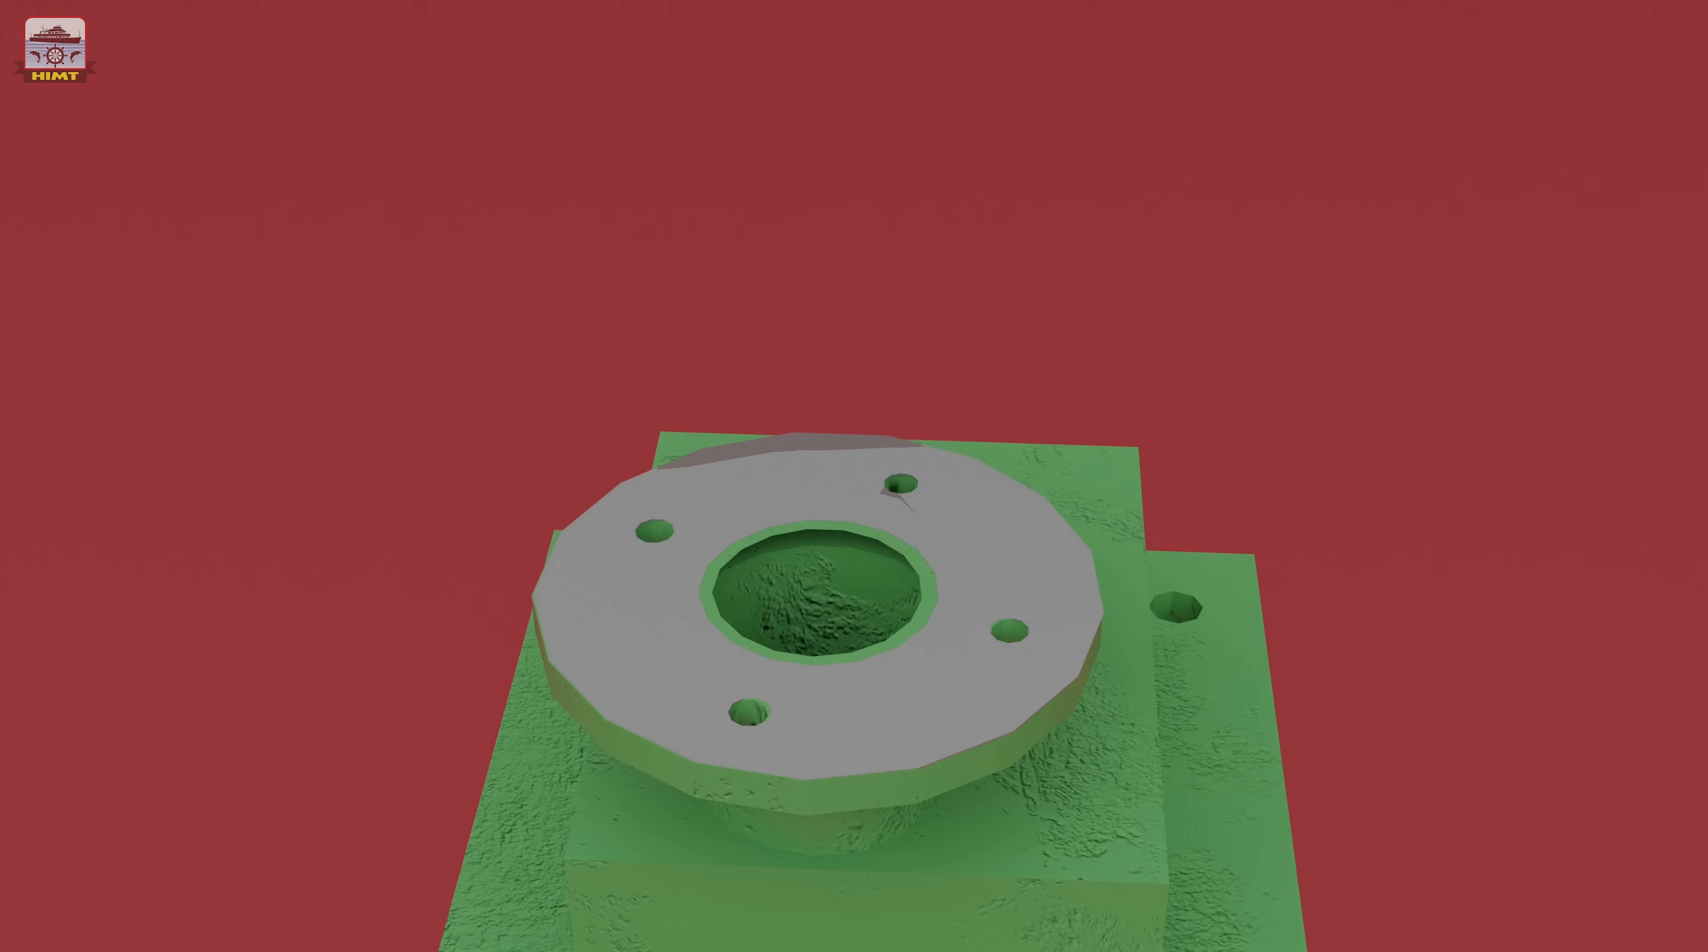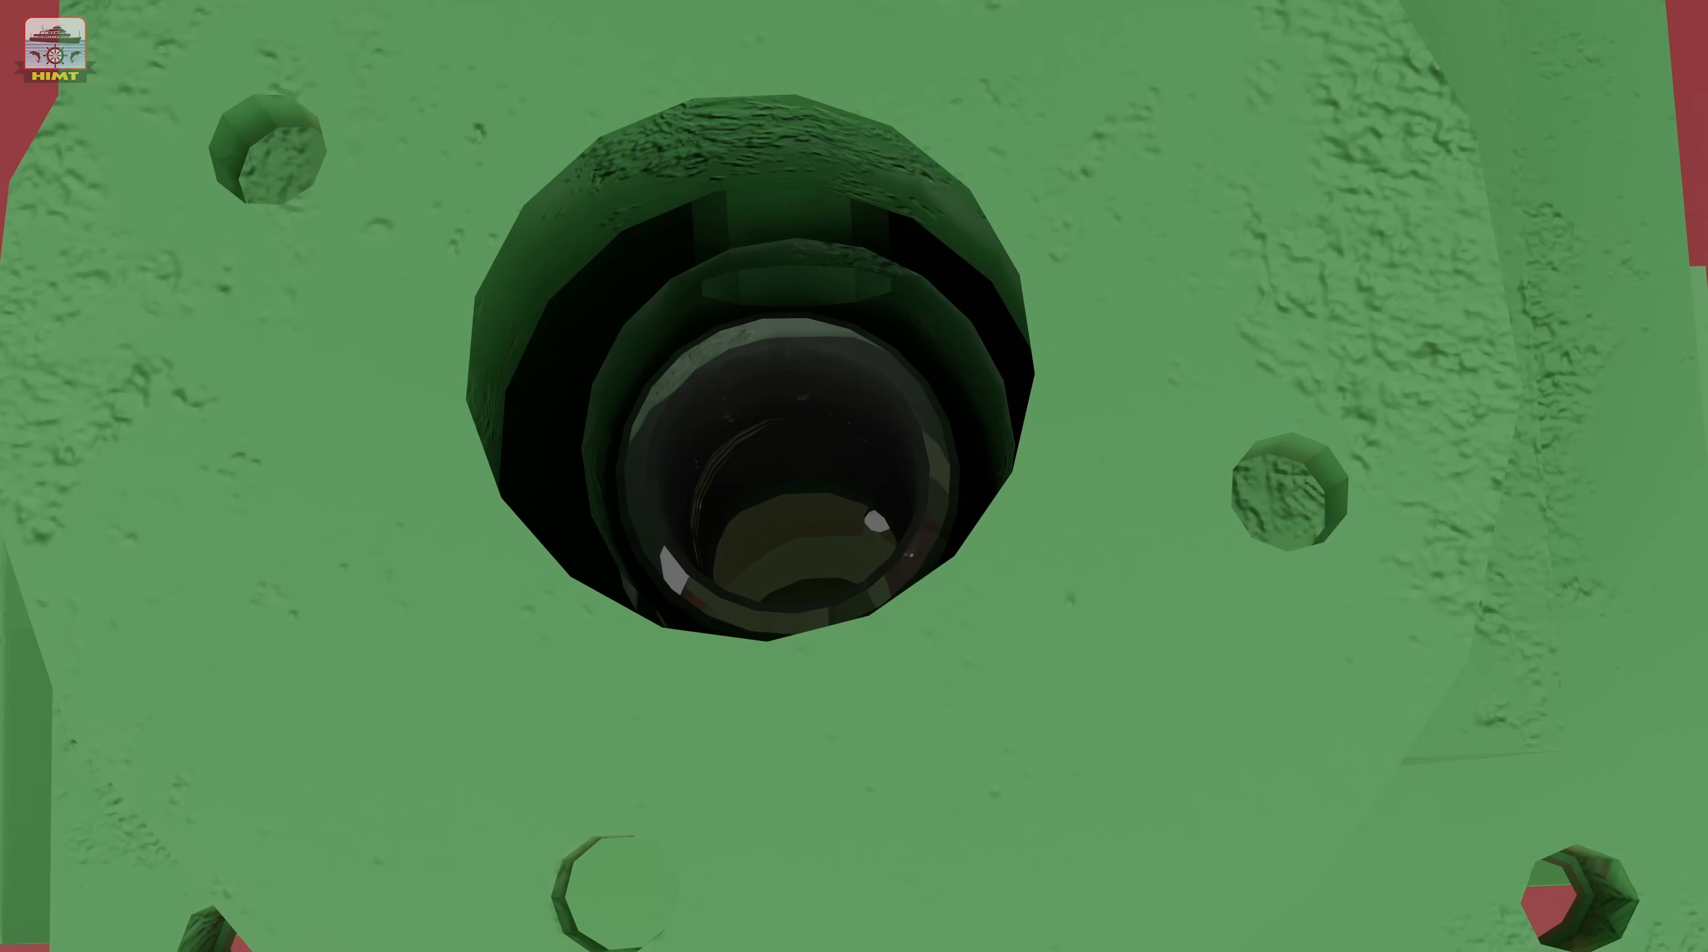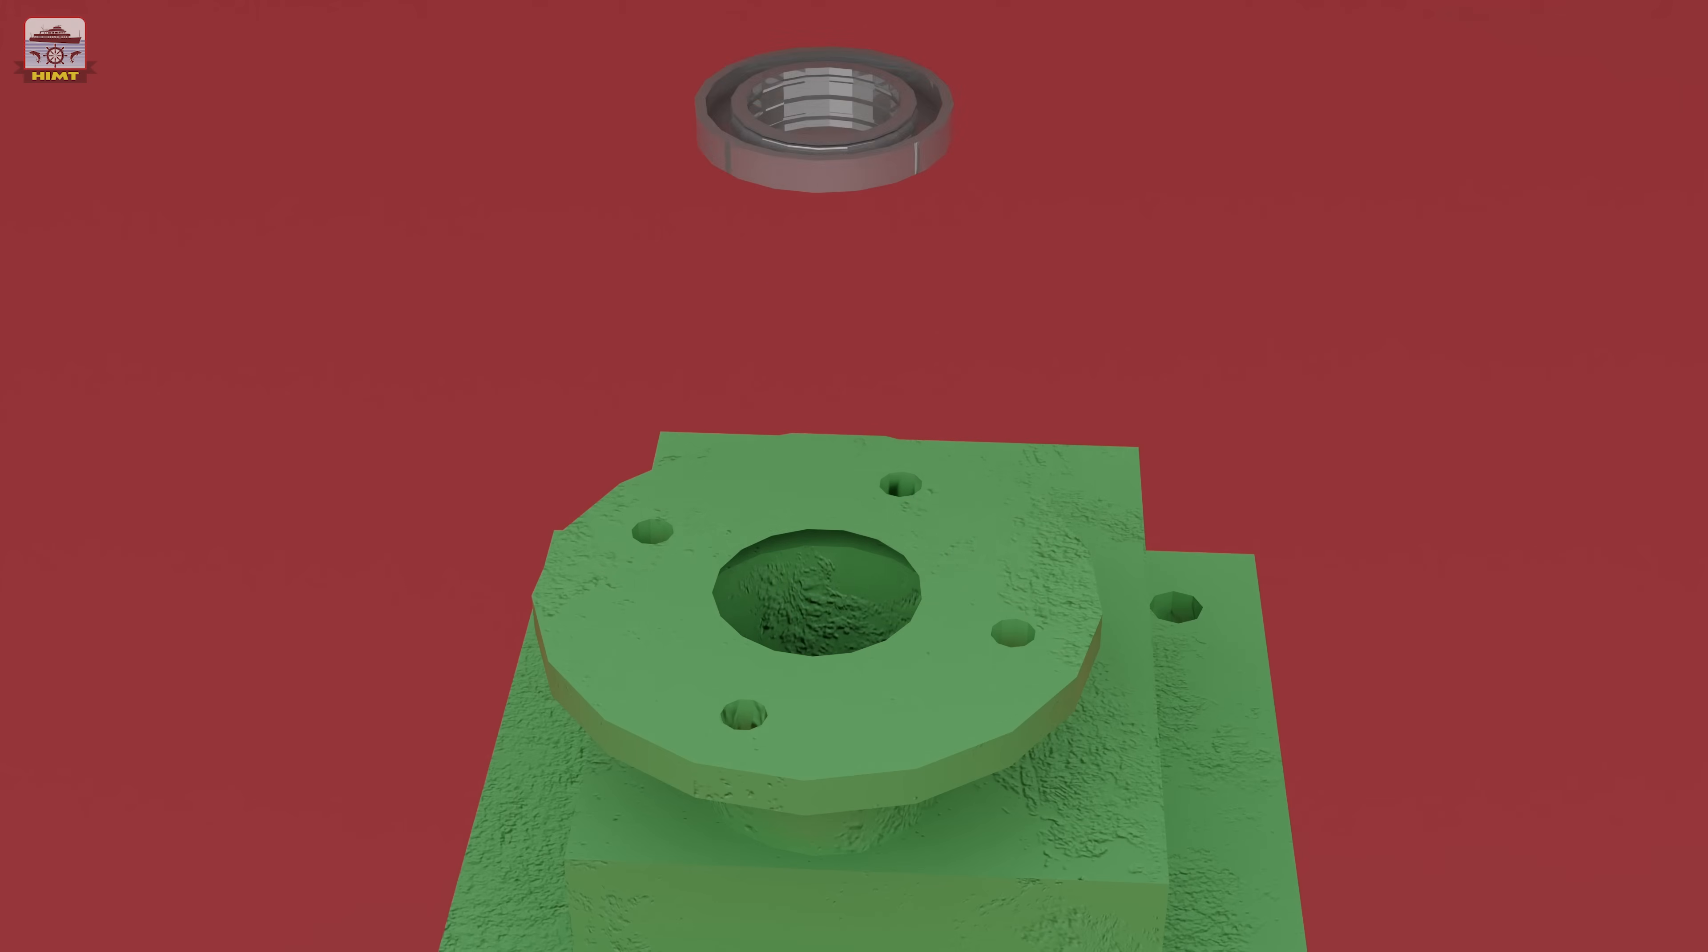Now, remove the flange gasket and remove the top spring retainer, revealing the spring and valve disc housed within the relief valve. Carefully extract the spring and then take out the valve disc.